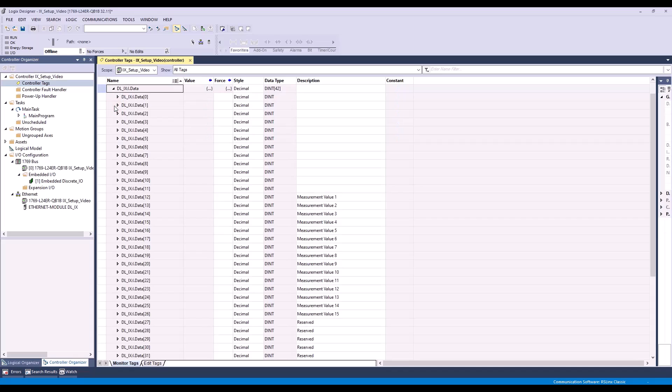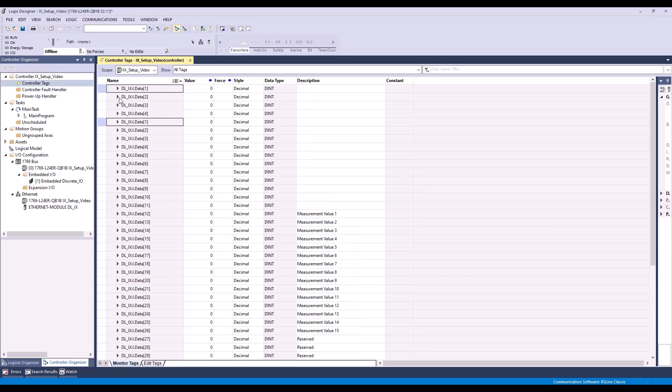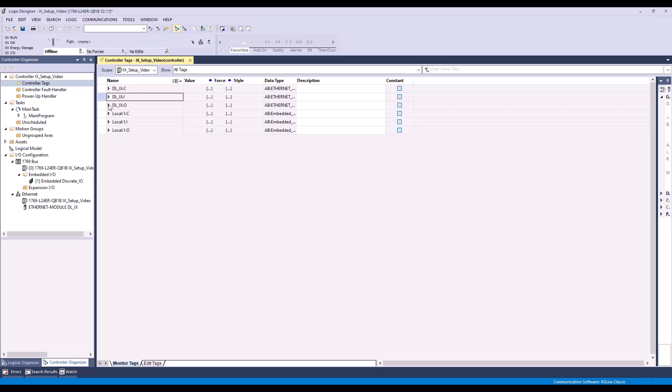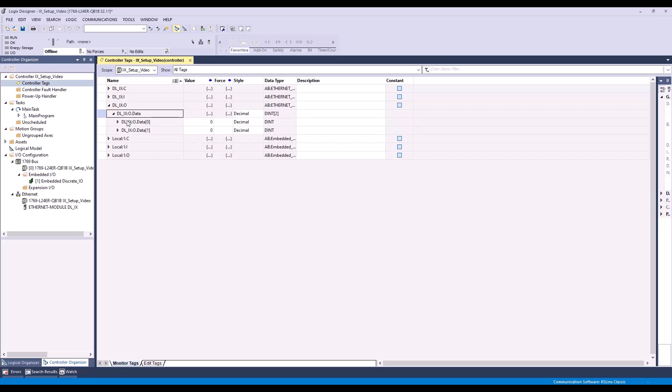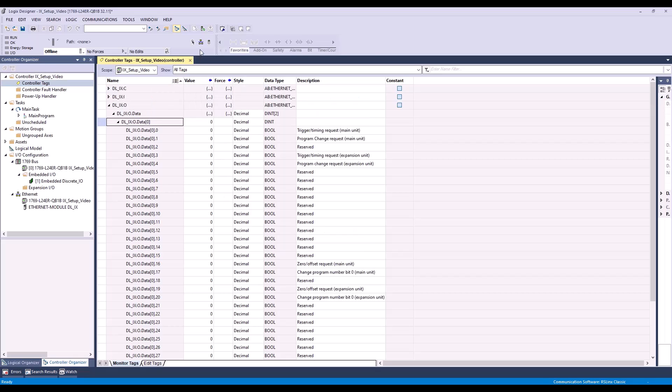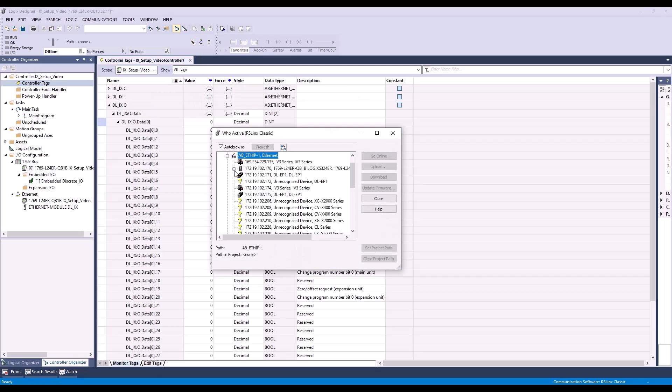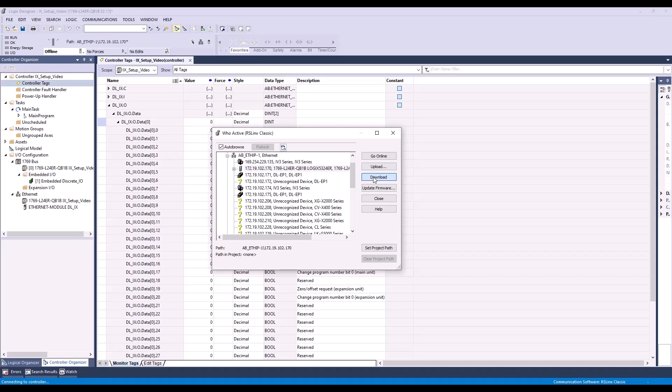Expanding DL IX iData will show that the tags we imported have been applied to the module we created. This is the data sent from the IX to the PLC. If we expand DL IX oData, we'll see the data we can send to the IX from the PLC. Now we can click the WhoActive button, find our PLC, and click Download. Click Download again, and this will put us online with the PLC.